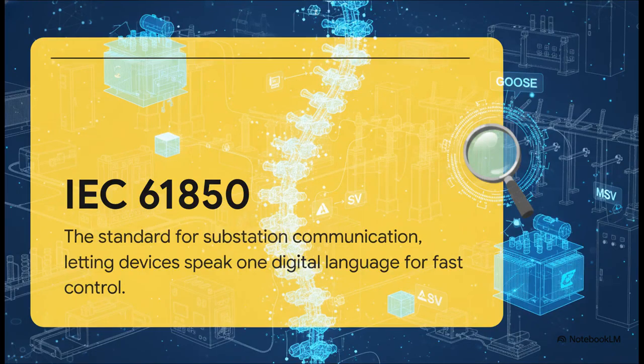And at the very heart of that nervous system is IEC 61850. Now, this isn't just another standard. It's the digital backbone of any modern substation. It's what allows all the smart devices, or IEDs, from totally different manufacturers to talk to each other over a network. They're all speaking the same digital language for unbelievably fast and reliable protection.